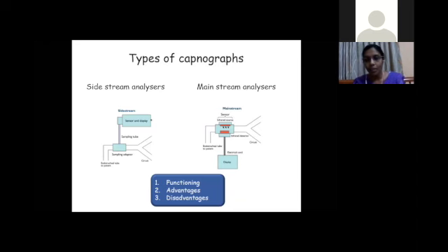These tubings are around 6 feet long. The tubing material should not absorb carbon dioxide, so they are made of Teflon. Water vapor can clog the tubes. Therefore, there should be a water trap for collecting the water vapor. The advantage is it's lightweight. And the problem with mainstream analyzers, that is the heating that I'll tell about later, is not there with the side stream analyzers.